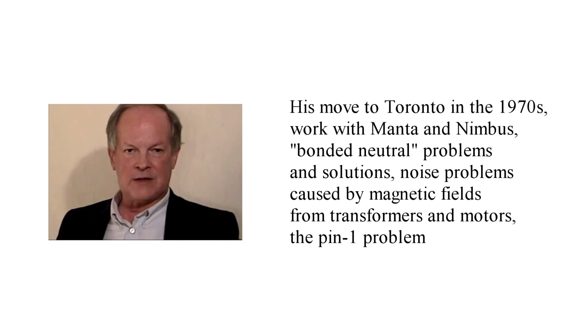Zero frequency means the motor is stopped, basically. Well, what was happening is they had wired this three-phase delta with no ground in the pipe, which I don't know how that ever got past the inspector. The ground current coupled through the elevator motor into the steel frame of the building was going everywhere as an H field, and it was all this high-frequency crap that went way up above 20 kilohertz.